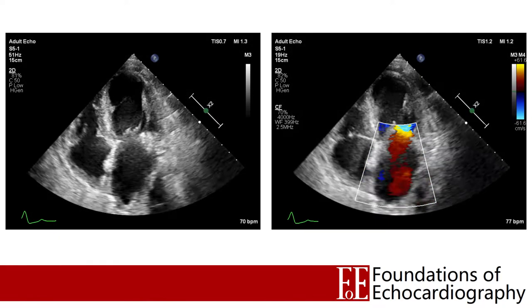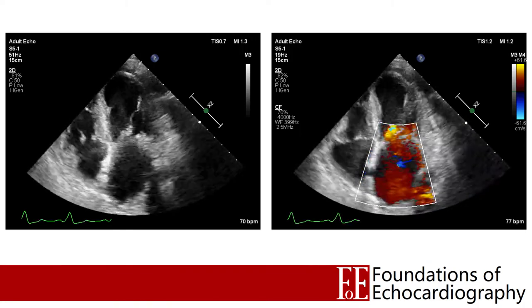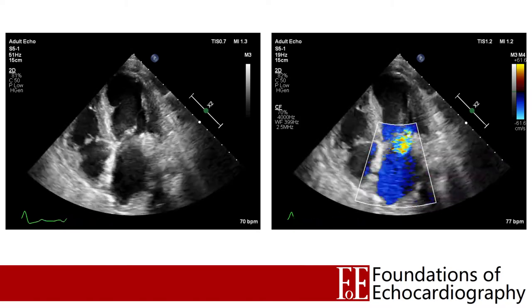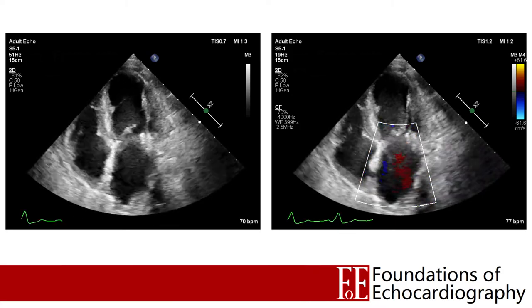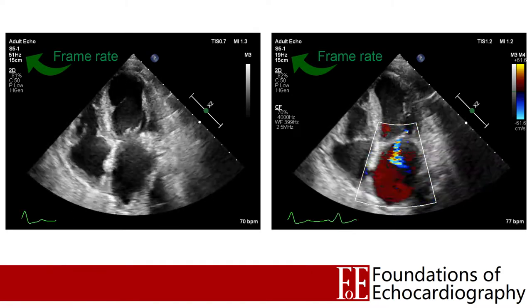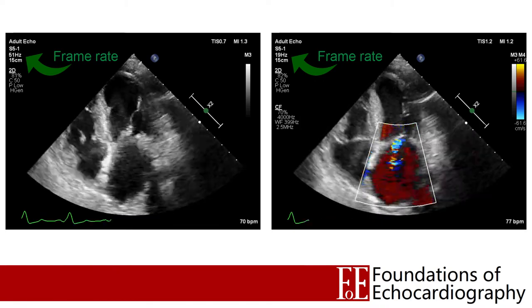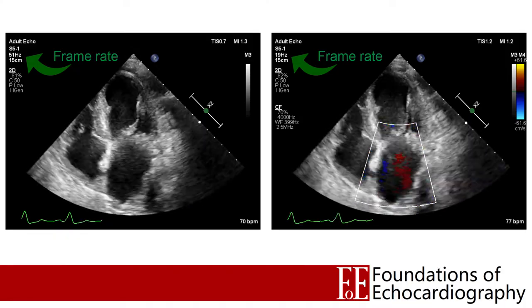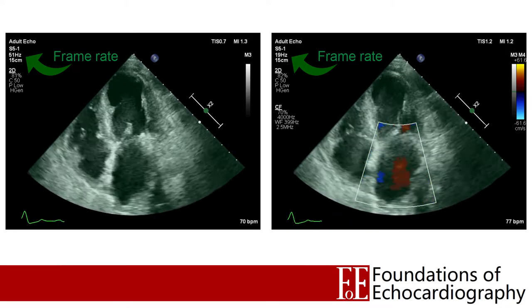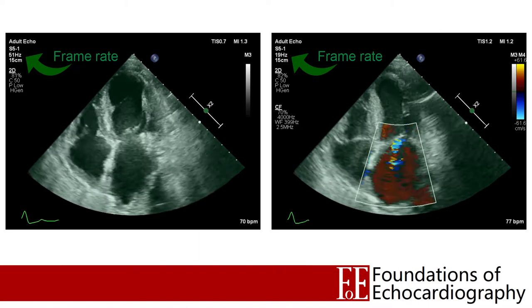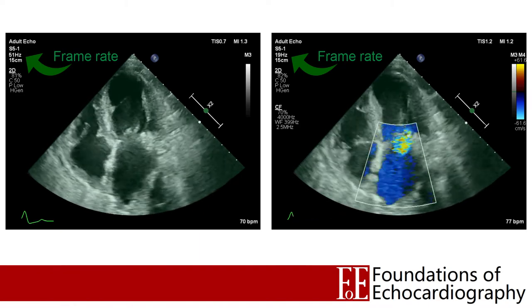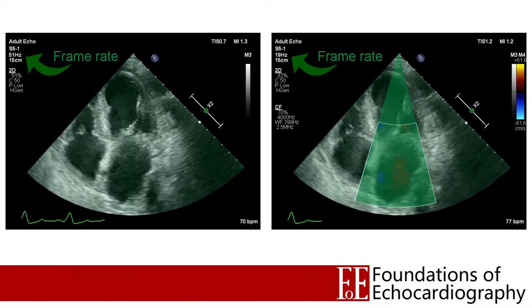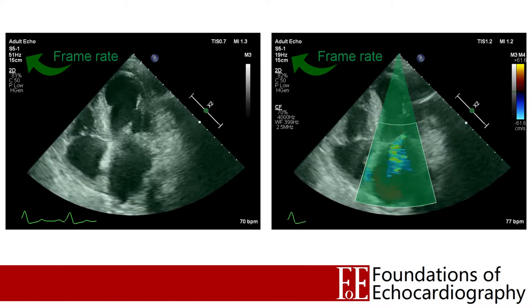The second limitation we need to consider is the impact of colour flow mapping on the frame rate. Here we have two apical 4 chamber views side by side with identical sector width and depth, but the image on the right has the addition of a colour box over the left atrium. Without the colour box we've got a frame rate of 51 frames per second, and when we add the colour box our frame rate drops to 19. Why is this occurring? The scanlines passing through the box must be scanned multiple times in order to gather enough information to calculate the phase shift and hence estimate the velocity of the blood travelling in that area.